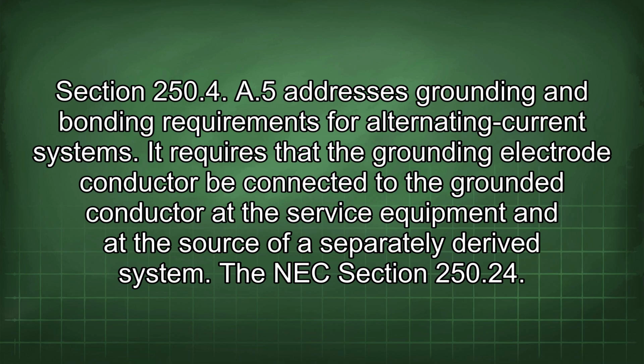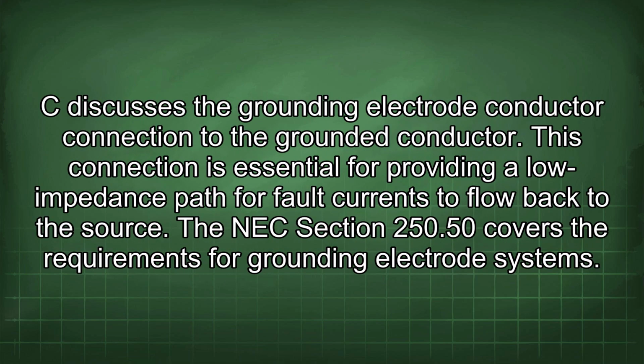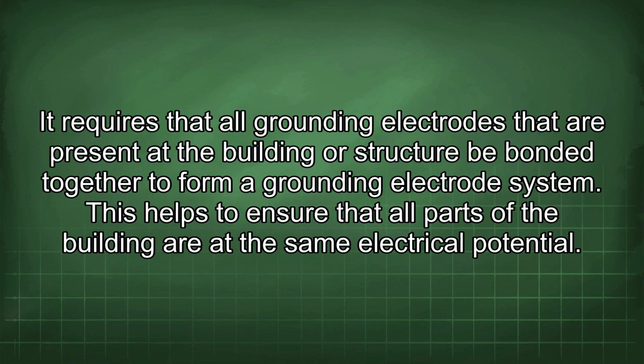The NEC Section 250.24(C) discusses the grounding electrode conductor connection to the grounded conductor. This connection is essential for providing a low impedance path for fault currents to flow back to the source. The NEC Section 250.50 covers the requirements for grounding electrode systems. It requires that all grounding electrodes that are present at the building or structure be bonded together to form a grounding electrode system. This helps to ensure that all parts of the building are at the same electrical potential.